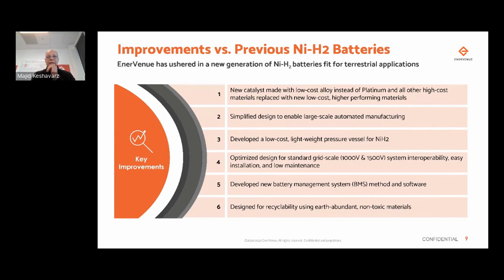We have developed a DC block for grid applications. Both 1,000 volt and 1,500 volts are available. We also have developed a battery management system, both firmware and software, suited for this type of battery, which is very different than lithium ion. The way we charge it, discharge it, is different. For example, with lithium ion, we do CC, CV. In this case, we always use CC, constant current or constant power, charge and discharge, so it's operated differently. And from get-go, we designed it so it can be recyclable using non-toxic materials as well, being environmentally responsible.